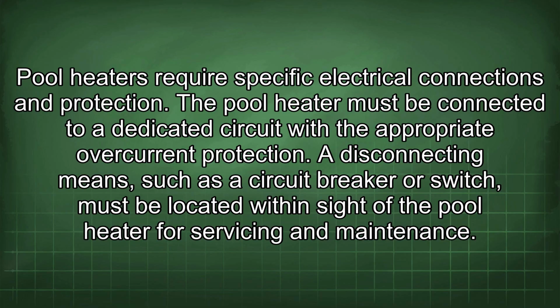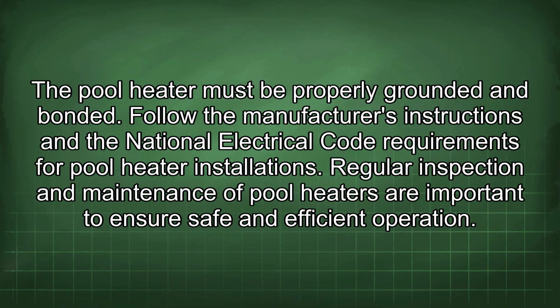The pool heater must be connected to a dedicated circuit with appropriate overcurrent protection. A disconnecting means, such as a circuit breaker or switch, must be located within sight of the pool heater for servicing and maintenance. The pool heater must be properly grounded and bonded.